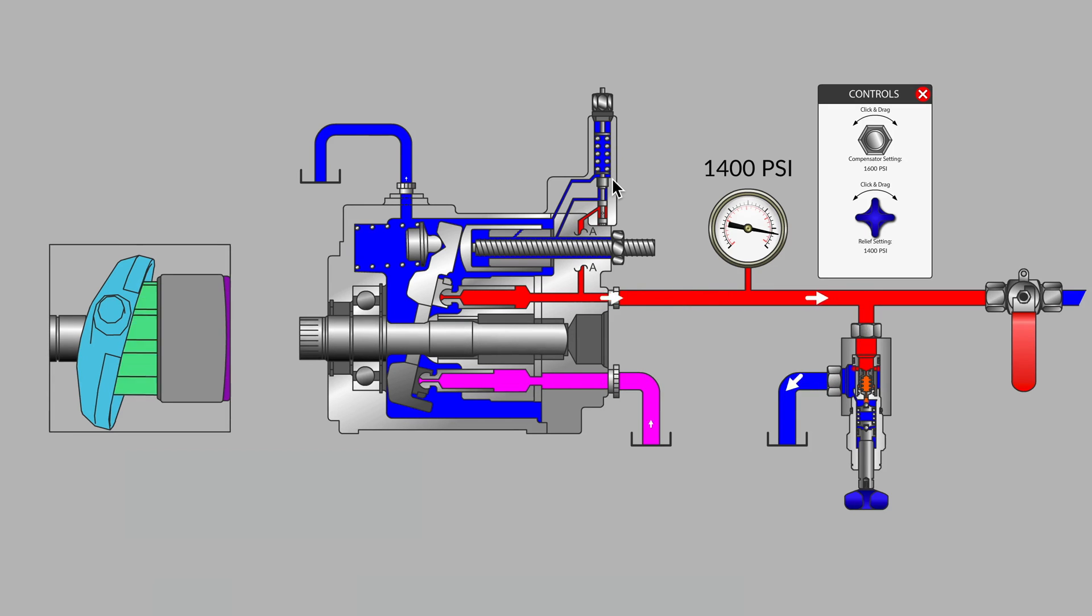But at this moment, we can see that the pump's swashplate angle has remained at the maximum angle, that our pump is in maximum displacement mode, and that all of our pump's flow is passing through the relief valve.